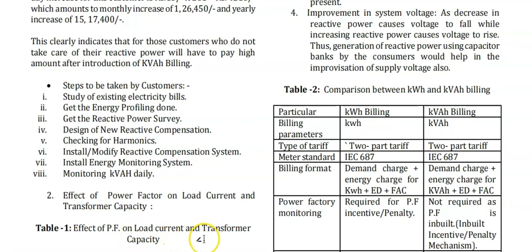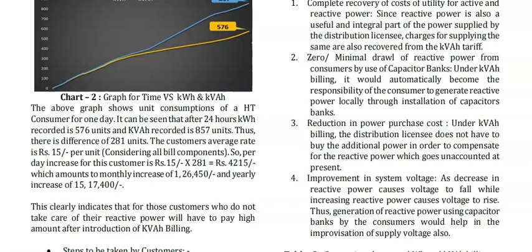Improve power factor to unity. Benefits of kVAh billing: complete recovery of the utility's cost for active and reactive power. Since reactive power is also a useful, integral part of power supply by the distribution licensee, the charge for supplying it is also recovered from the kVAh tariff. Zero or minimal reactive power drawn from the utility by the consumer through the use of capacitor banks. Under kVAh billing, it automatically becomes the consumer's responsibility to generate reactive power locally through the installation of capacitor banks.